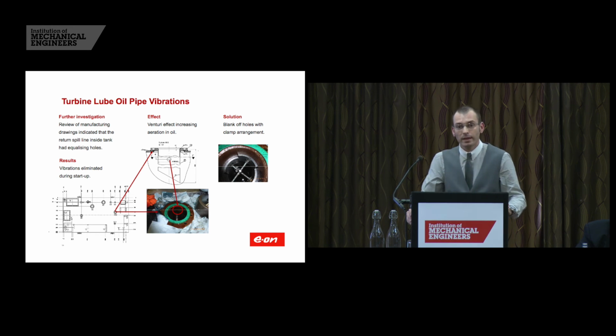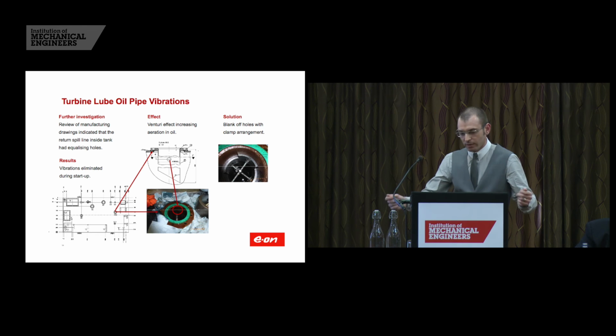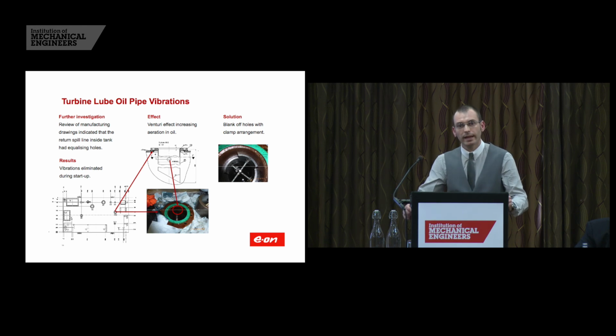What can be learnt from this? Well, if we did a factory acceptance test, would we have seen this? Would we have met this? If the SQS engineer was out there, he would have taken a site drawing and compared it against an as-built piece of equipment, and the two would have matched. So I would say that this one would have slipped through the net even if we had inspected the tank, unless you've got specific knowledge of a system of this type.